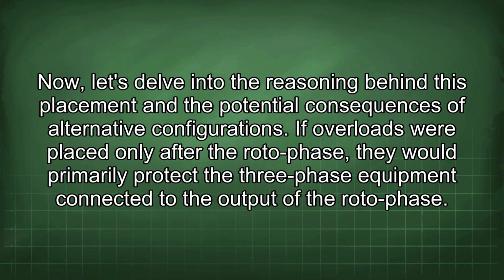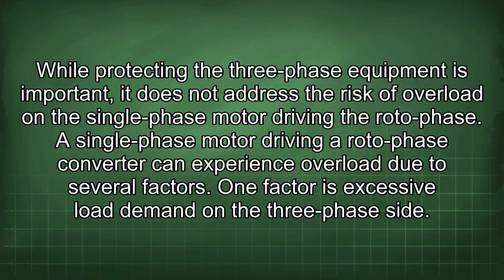Now, let's delve into the reasoning behind this placement and the potential consequences of alternative configurations. If overloads were placed only after the roto-phase, they would primarily protect the three-phase equipment connected to the output of the roto-phase. While protecting the three-phase equipment is important, it does not address the risk of overload on the single-phase motor driving the roto-phase. A single-phase motor driving a roto-phase converter can experience overload due to several factors.